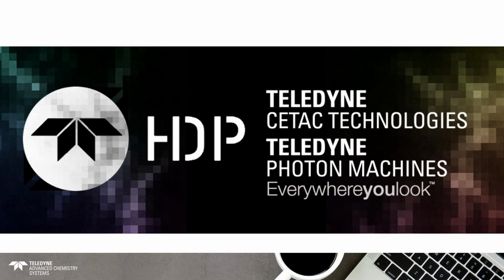And when I'm talking about basic functionalities, I'm talking about, for instance, calculating the peak statistics, or the single pulse response of the system, so that you have a really good understanding of the washout or the speed of your system. Also, I'll show you how to model the imaging parameters so that you increase the quality of the data, so you know exactly what parameters to use, both on the laser and on the ICP side, to minimize the downtime.